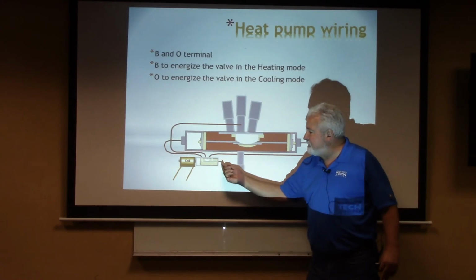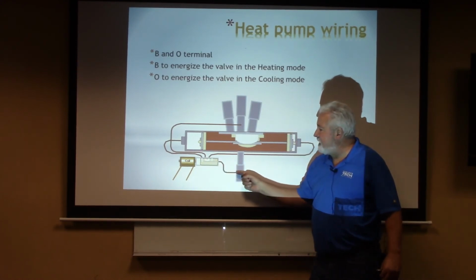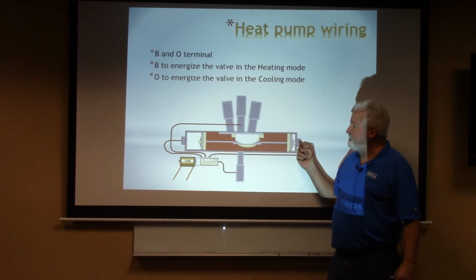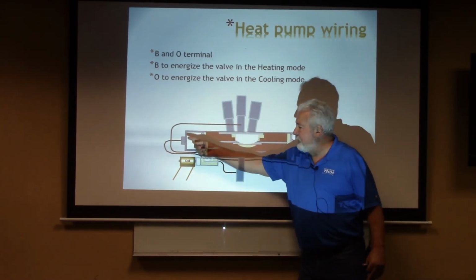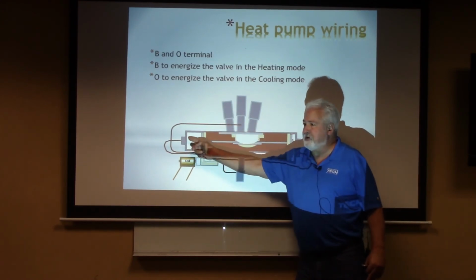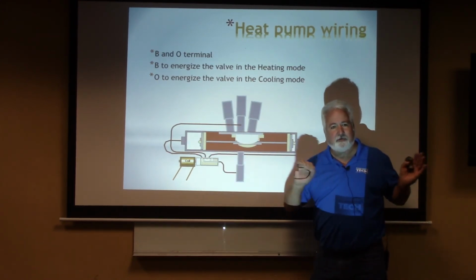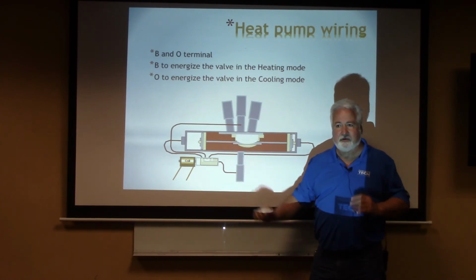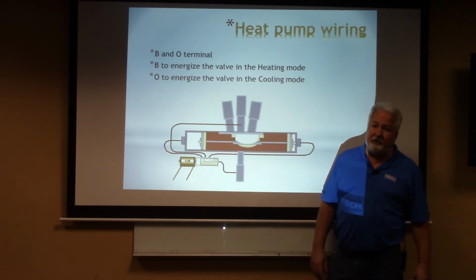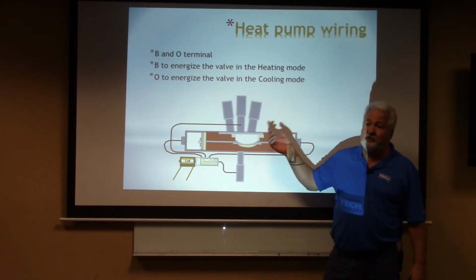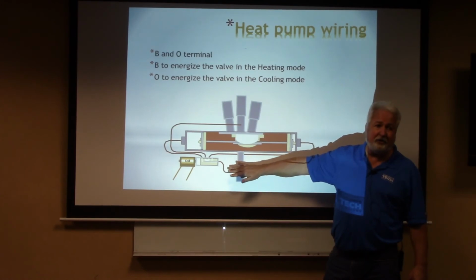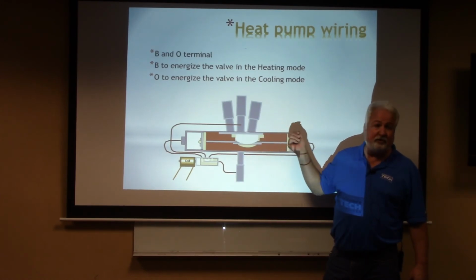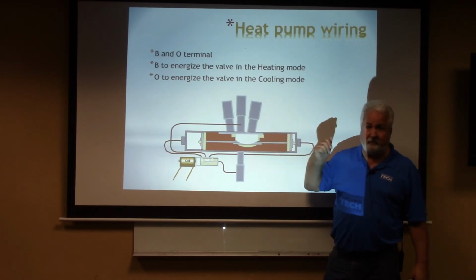If I energize this and shift it over, that high pressure gas now goes to this side, and the low pressure gas now goes to this side, and it shifts it back. Does that make sense? So these valves are electrically initiated and pressure operated. Electrically initiated, pressure operated. So if the valve doesn't shift, it may not be anything in your electrical circuit. It may be that you just don't have enough pressure to be able to get it to shift. Does that make sense? Good.